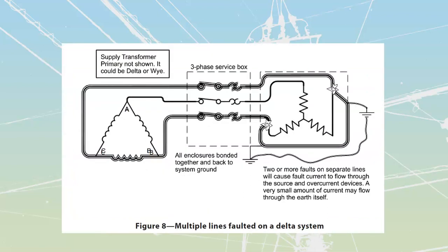If we have two faults, however, all bets are off. Over here we see that we've got two lines that have gotten accidentally grounded or attached to my bond system. As soon as this happens, we're going to have current supplied by one of my lines. In this case, it's my C line, and it's going to supply current, with that current having the option of going through these loads.